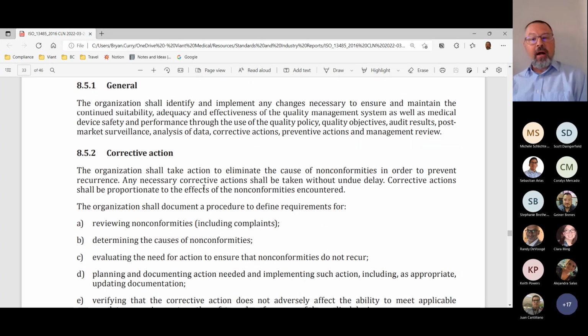So organizations shall ensure the suitability, adequacy, and effectiveness of the quality management system, as well as medical device safety and performance through the use of a lot of things that ultimately represent the sum total of your quality management system. So it says, here's how you use your improvement system. And the improvement system captures both corrective and preventive action. Number one, you're going to use this improvement system to actually improve the quality management system itself. Whether you're improving it because you determined in the previous clause that it is fundamentally not effective, well, then here's the system that you're going to use to fix it.